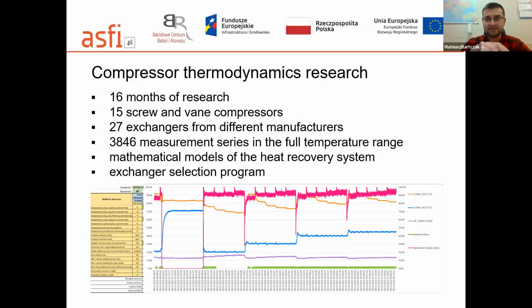What does it mean? We tested different flows on the water side across the full temperature spectrum from 10 to 50 degrees. We measured the oil flow using Coriolis flow meters. We measured the water flow and the temperatures on the oil and water sides. We got almost 1 billion measuring points, and we used them to create mathematical models of the heat part of a compressor.